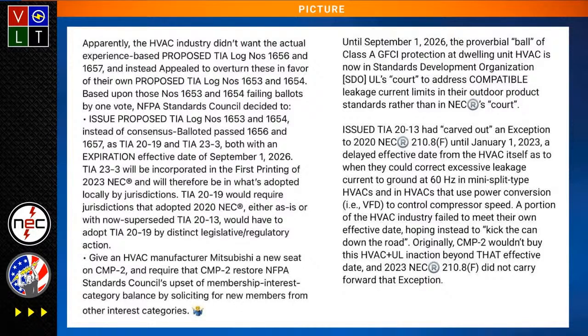They've clarified a lot over in datum planes and stuff like that. And what they did, which I thought was a pretty good job, the special GFCI and everything, they have that at a setting of 20 milliamps. That's just a round number they use there. The reason they did that is to clarify it from just a regular Class A GFCI device.